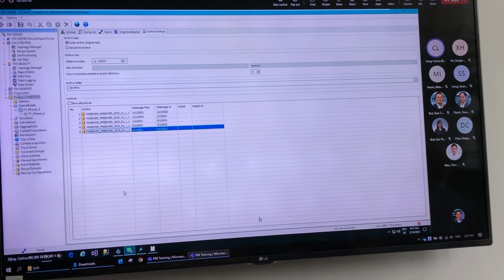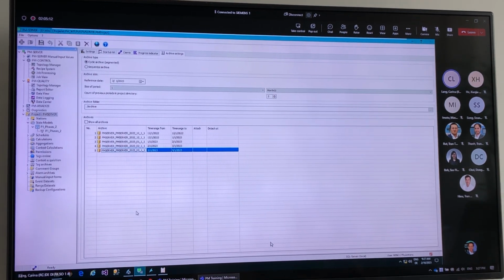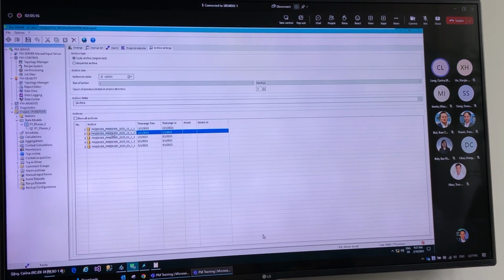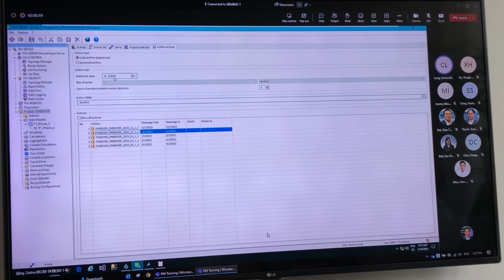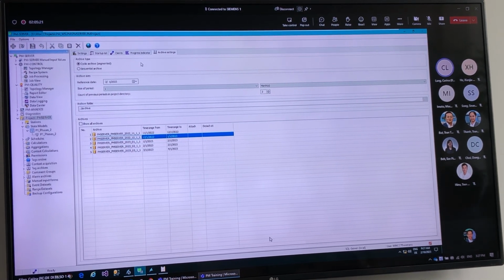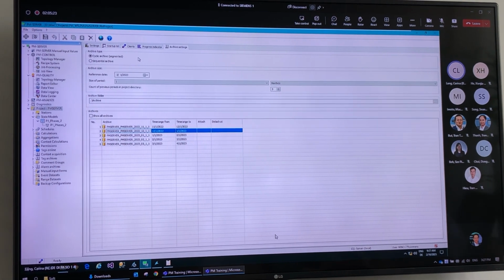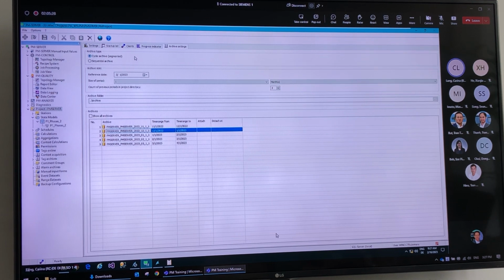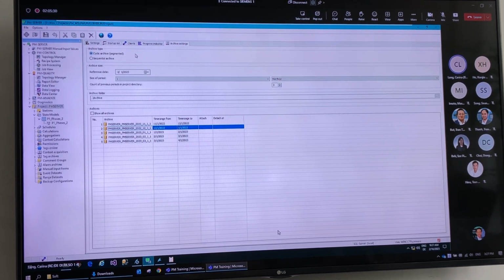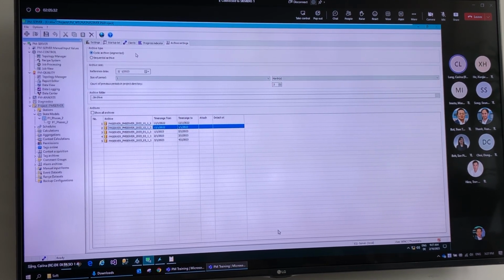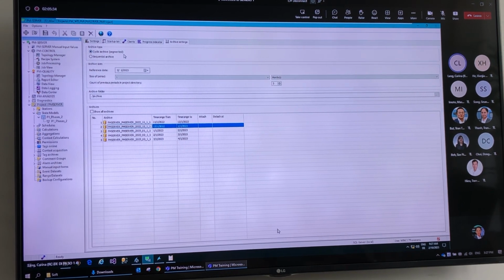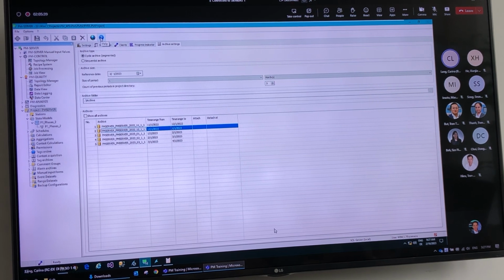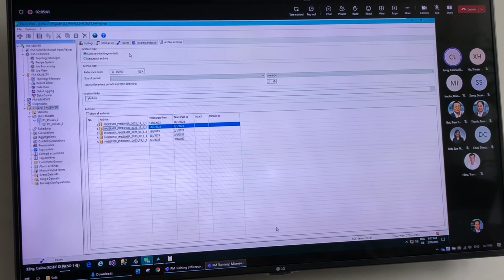So that means if you go to the project path and then you're wondering what all of these databases are, so these databases are for the archives, and there are different archive types available. So we have the cyclic archive, segmented, or the sequential archive. By default, always the cyclic archive is selected, and you can find some more information or some detailed explanation of these settings inside of the help of the PM server.